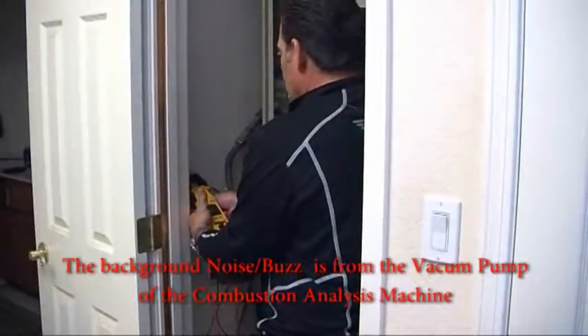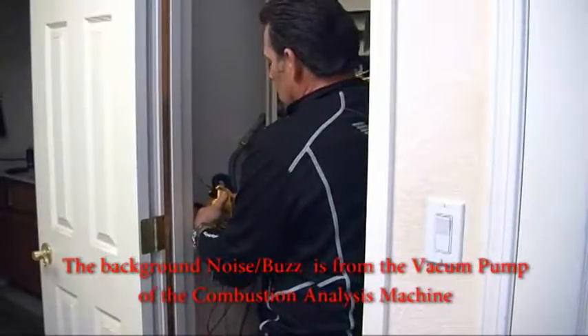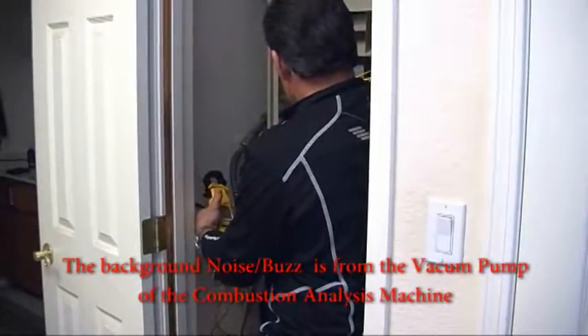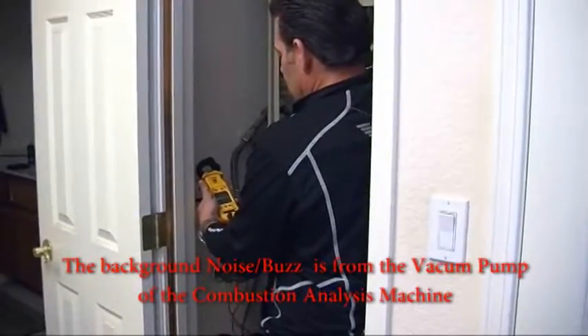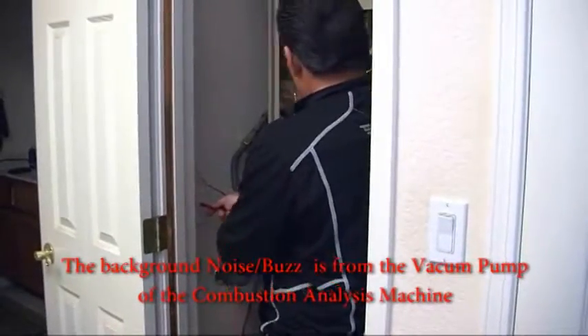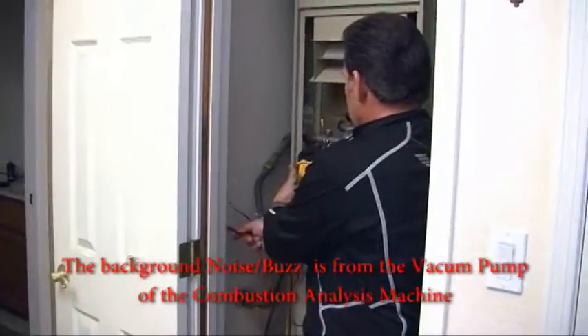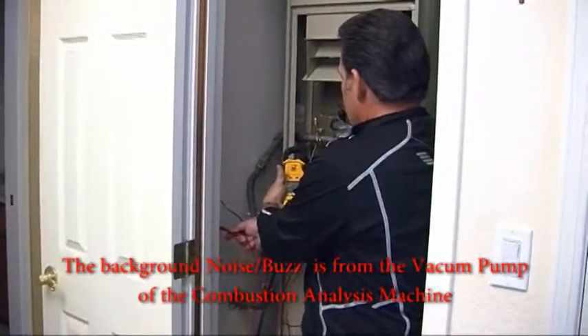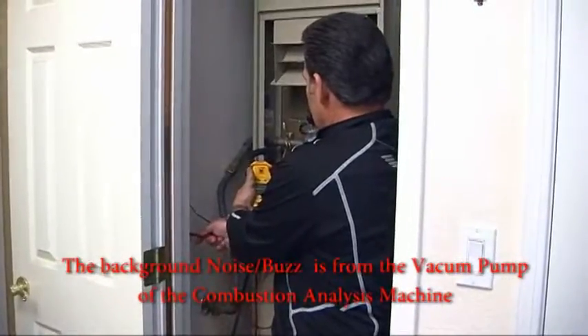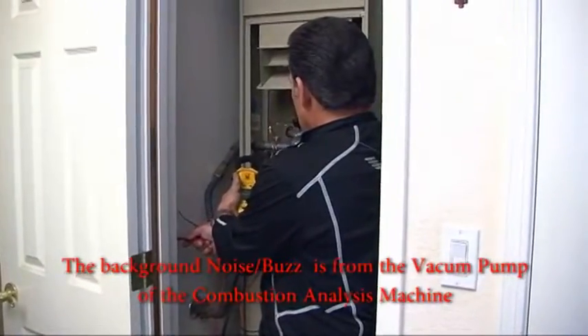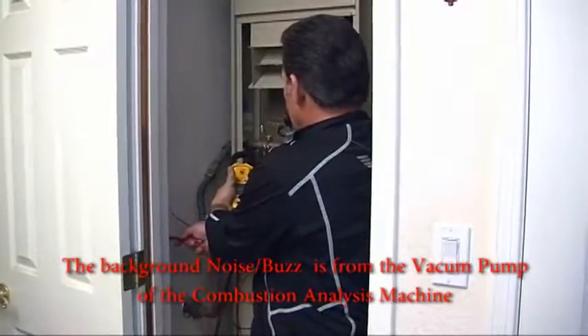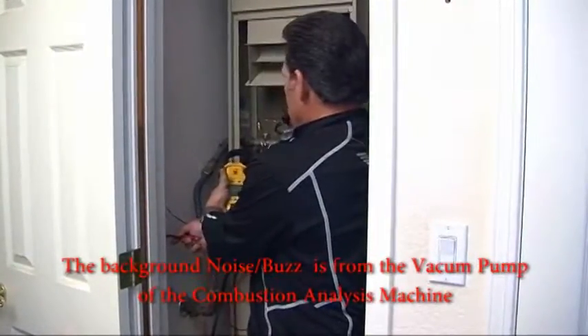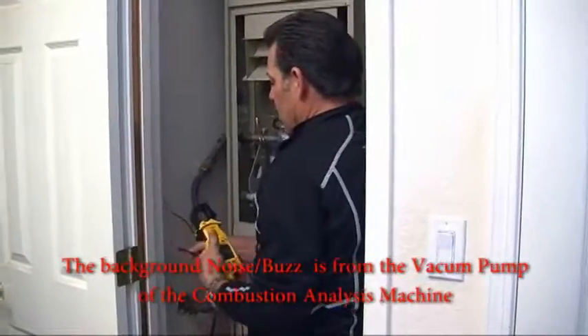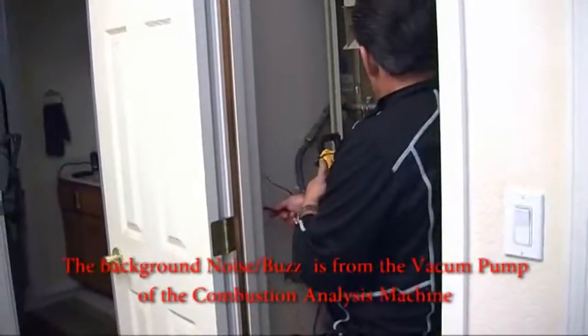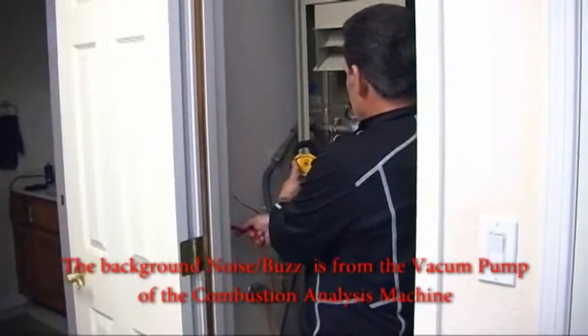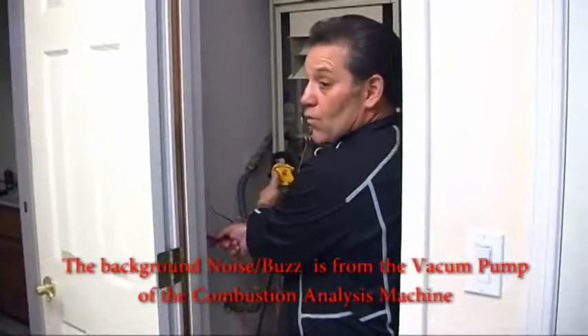So then I want to check my ground. I want to check my neutral to ground to make sure I don't have anything. I don't. Then I want to check my line voltage to ground. I have the same reading that I had earlier. I have 119.9. You can see I have 119.9. Now I'm going to check my ground to ground. I should have 0 there. And no voltage. Okay?